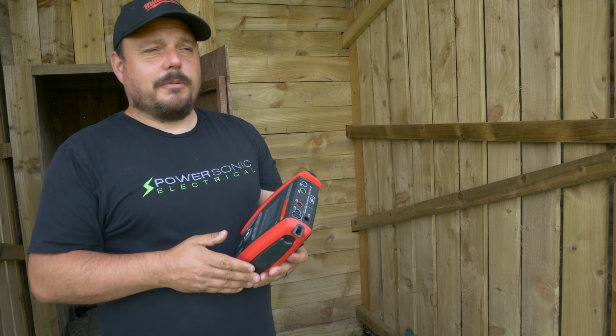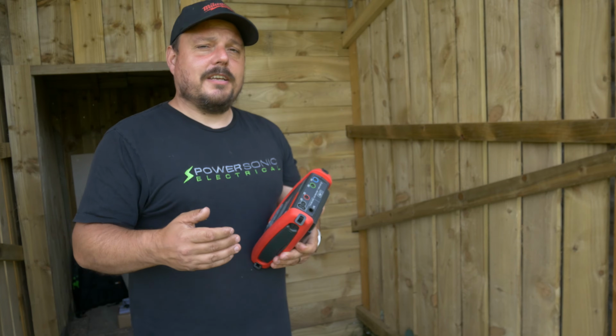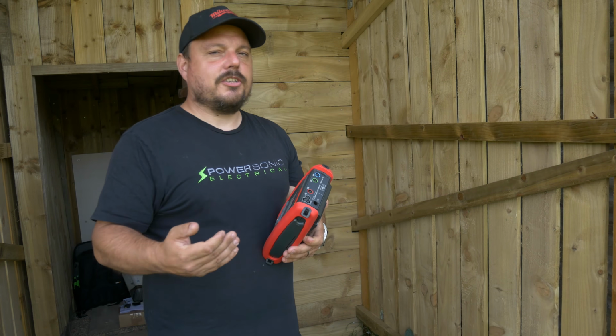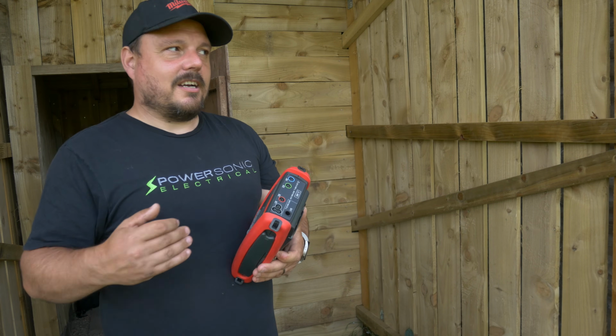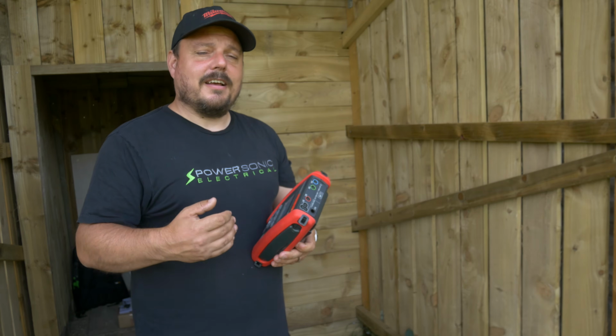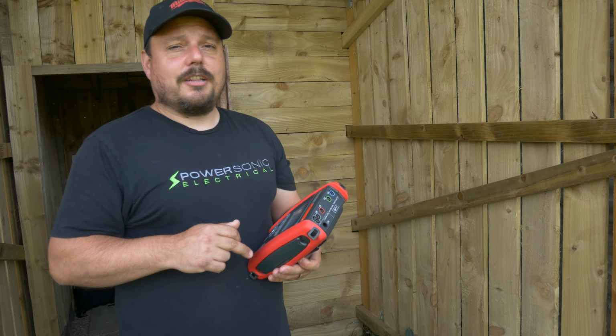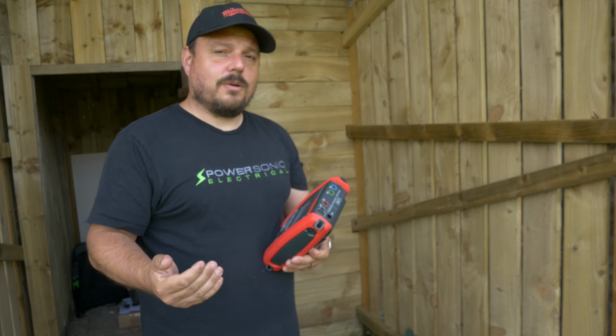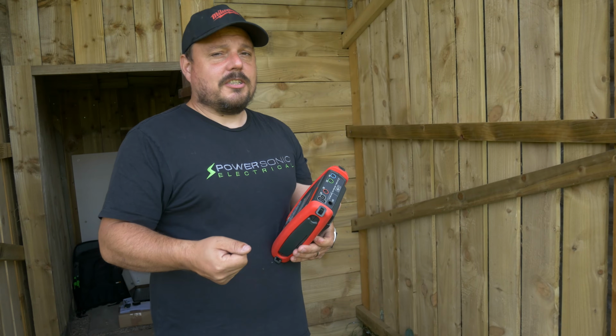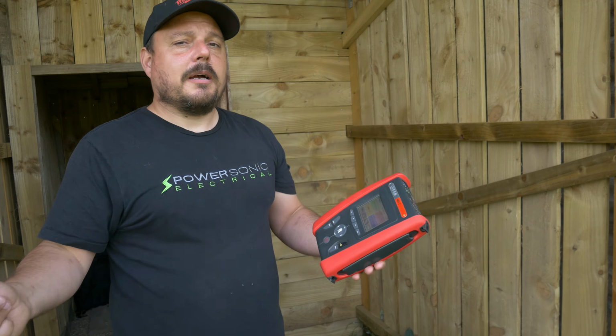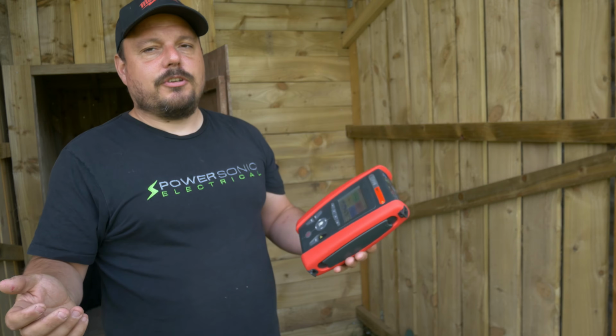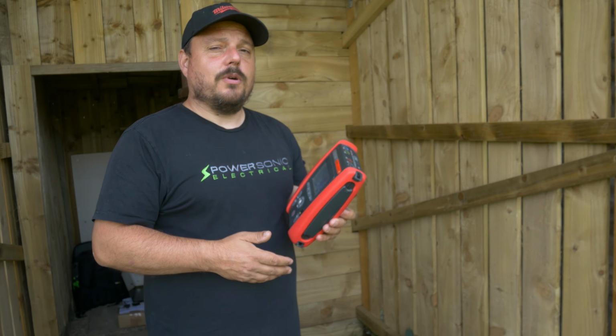Super duper importantly for us as solar PV installers alongside battery storage, people tend to want to go into island mode, and as such we need to have an earth electrode. This will do earth resistance testing in both the traditional way in terms of doing that live as a ZE measurement, and with the ground spikes that you can put out in the area around your earth electrodes and get a value of RA.